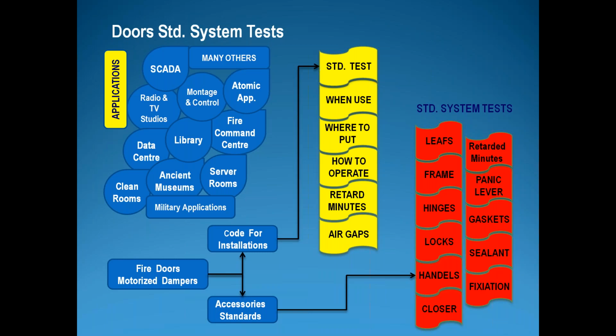And another thing is to have a low temperature of the door surface on the escape side. For our dampers, we have to be sure that they will be totally sealed, not 100%, no, but there are regulations for testing the dampers, to be sure that we select the minimum leakage.